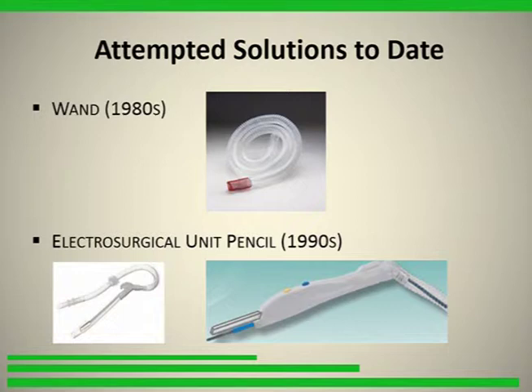the electrosurgical unit pencil, which is currently used, is a monopolar electrode, which means it can only be used for monopolar cautery, with an embedded 3/8 inch tube, flexible tubing, usually connected to an inline filter and then to the wall suction, although more commonly today they're adapting it to a direct connection to the smoke evacuator, standard smoke evacuator.